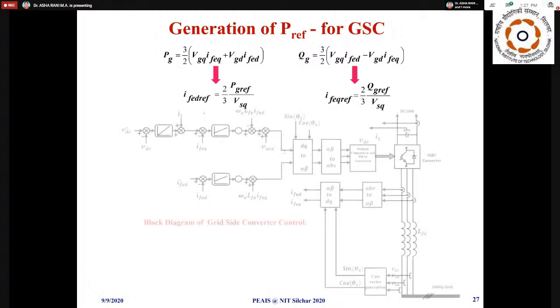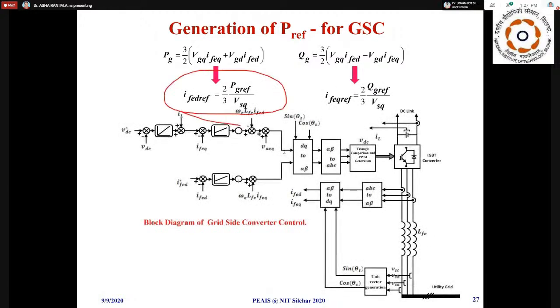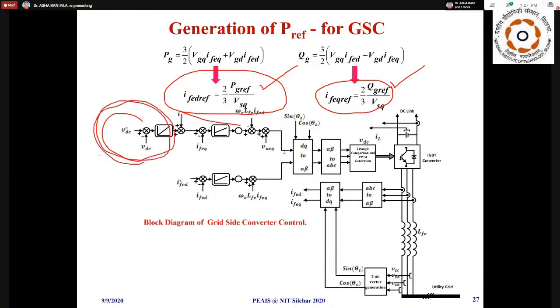Similarly, on the grid side, a similar procedure is there. You find out how much power you can pump from the grid, or whether you want reactive power from the grid, or want to pump anything into the grid. Based on all these things, we fix the loop. One important thing to note is the GSC's main role is to control the DC link voltage. If your DC link is 400 volts, you give this 400 volts as reference, compare it with the actual, and this loop will run. This is a fundamental thing.